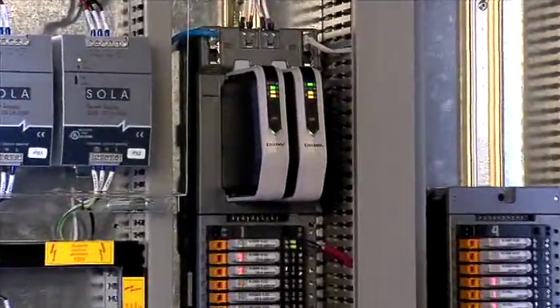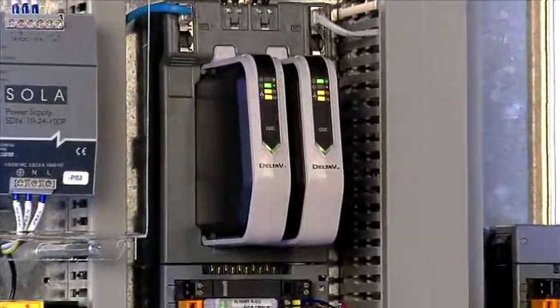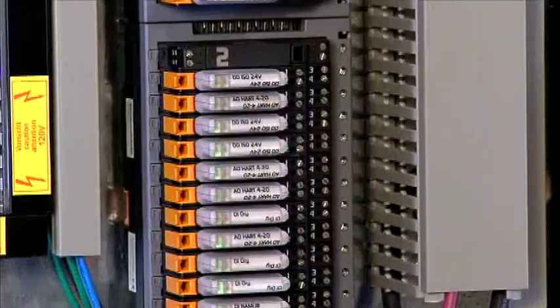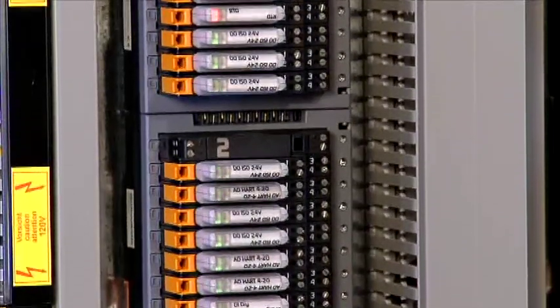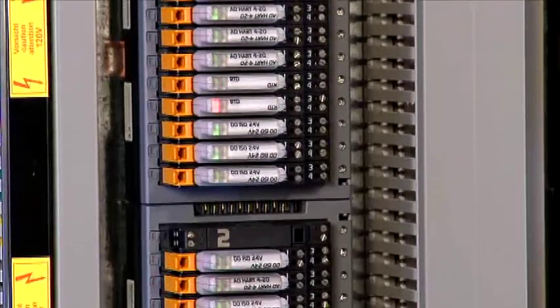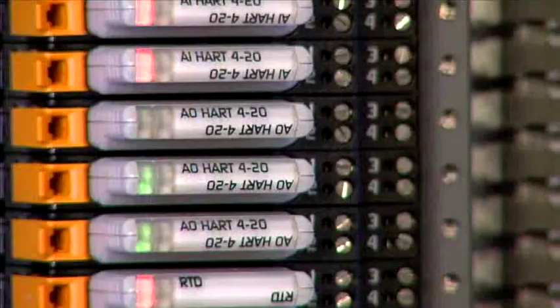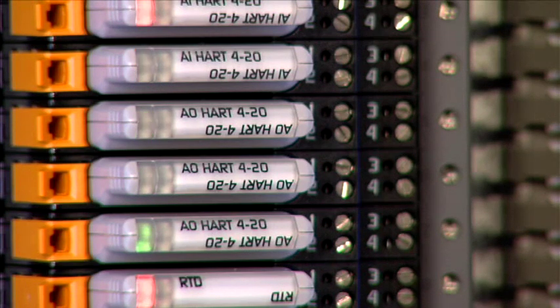Another important component is the CHARM I/O card, or CIOC, which supports up to 96 individually configurable channels, providing the redundant communications between the CHARMs and the DeltaV S-series controllers on the control network.